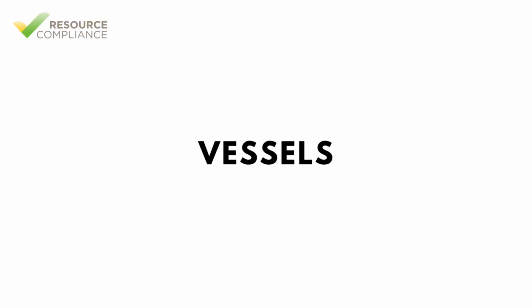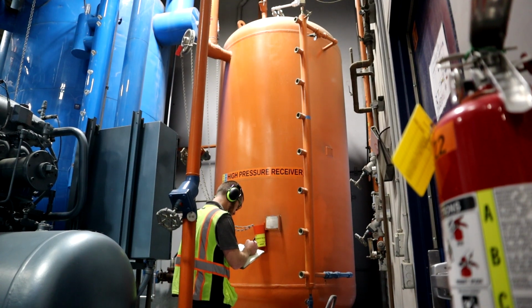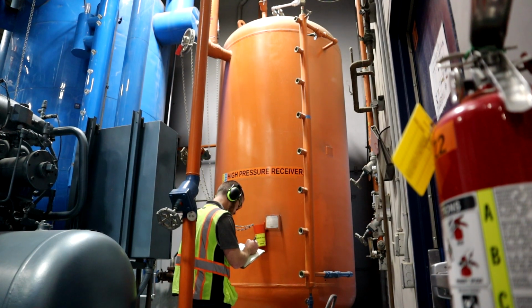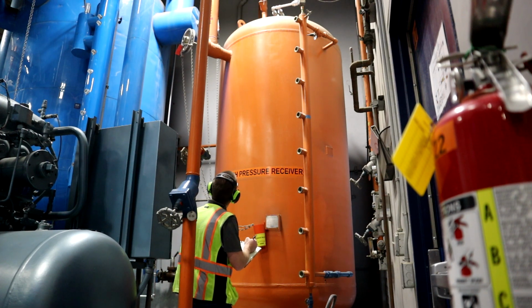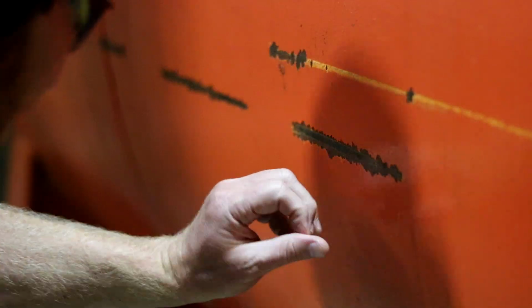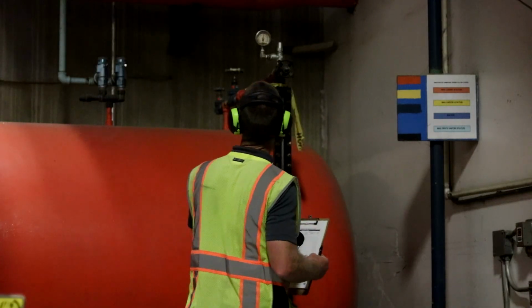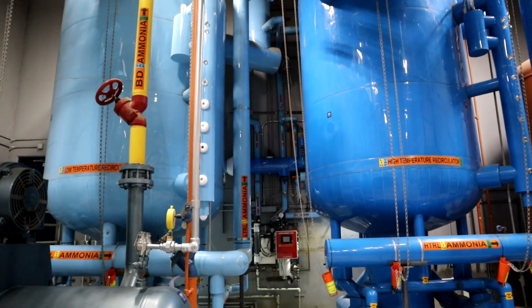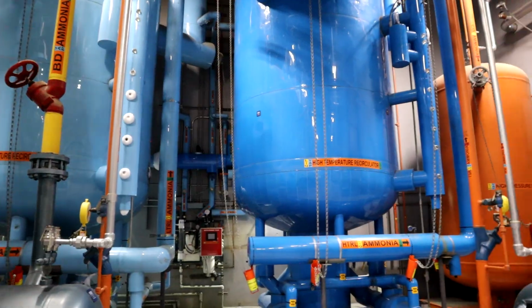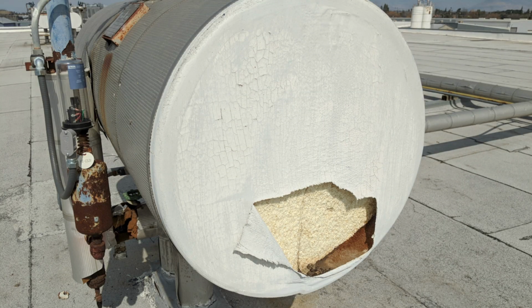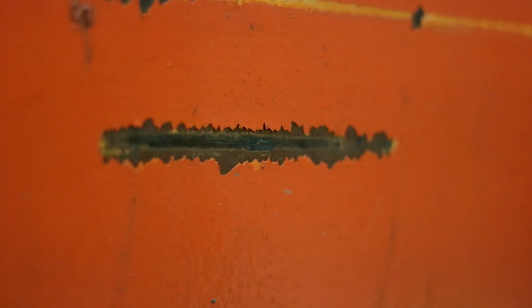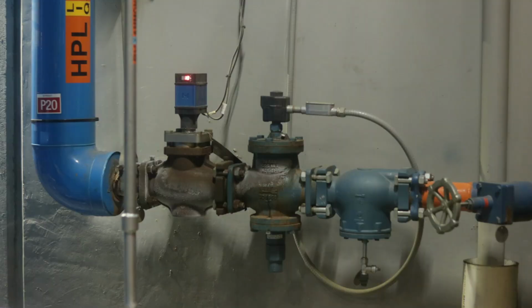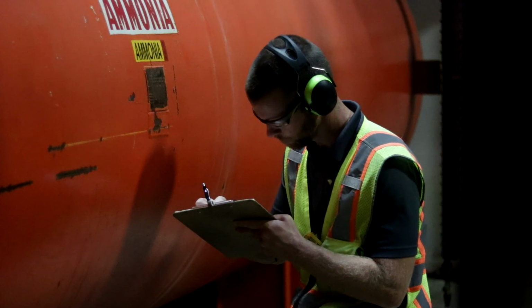Pressure vessels must be inspected at least annually. However, for the main system vessels, such as high-pressure receivers and recirculators, it is recommended that they be included in the system lock inspection. At minimum, the annual visual inspection will check for surface corrosion and pitting, damage to sight glass metal surfaces, moisture in the insulation that could lead to corrosion under insulation, damage to insulated vessel's protective jacket, paint degradation, proper anchorage and support structures, excessive vibration when liquid is being supplied, and a legible ASME stamped nameplate.